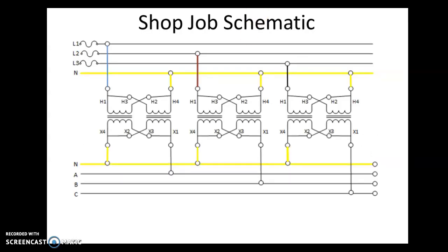Here you can see that a little bit better. So if I have light bulbs connected on the end, then I come out of phase A through a light bulb and then back into neutral, okay, there's only one path for that current to flow no matter where we follow it back to. Once we get to the transformer, we see the X1 to X3, okay, X2 to X4, and so on, on both sides. So we have a Y-connected system on the primary, and we also have a Y-connected system on the secondary. What does that mean for us?